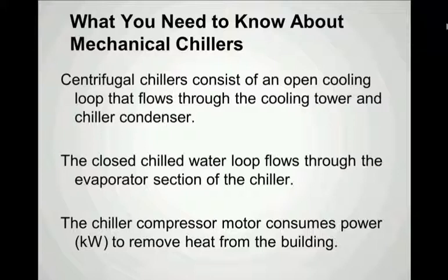So for now, though, what do you need to know about mechanical chillers? First of all, that the centrifugal chillers consist of an open loop, which flows through the cooling tower, and then a closed chilled water loop that flows through the evaporator section of the chiller. And further, that the chiller compressor motor consumes power, electric power as measured in kilowatts, to remove heat from the building. So that's the big energy consumer, is the power required to drive the chiller compressor motor to accomplish this heat transfer.